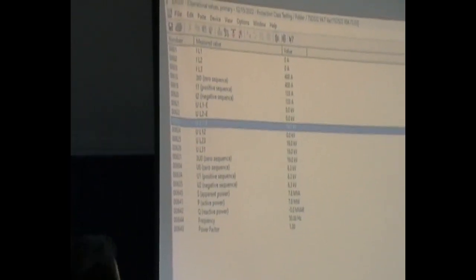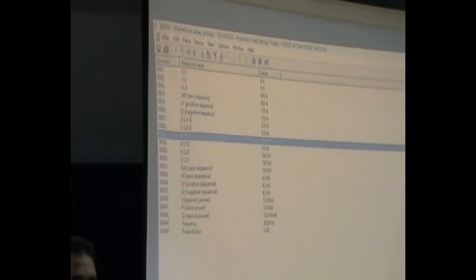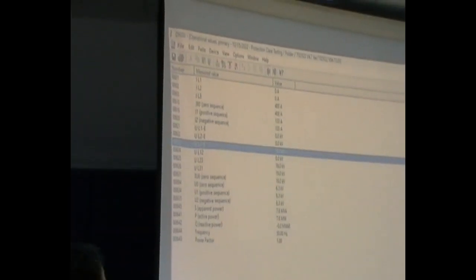Now we'll inject in the blue phase. Again, in the relay, it shows the blue phase of 400 ampere, and the same goes for the voltage. Now this is normal injection. I could be injecting some current that I wanted to see in the sequence elements: positive, negative, and zero sequence.